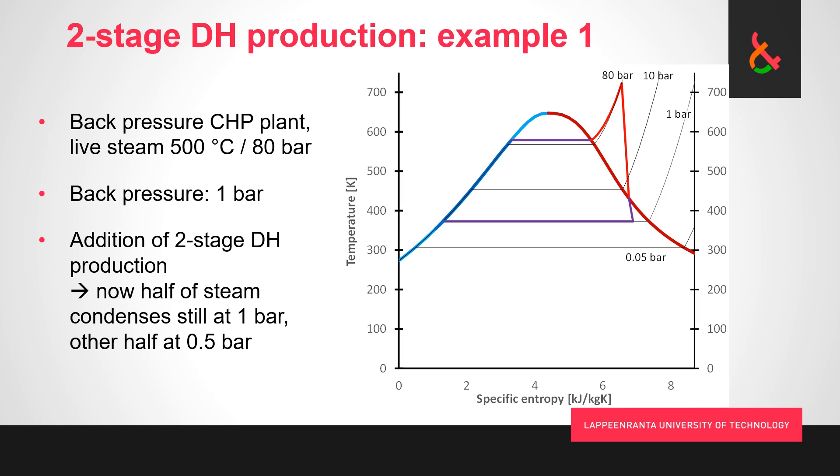We can't get to 0.05 bars, but what we can do if we add two-stage district heating production is that with the addition of a second condenser, the one that operates at lower pressure preheating the return water, we might get to around half a bar. Not a huge deal perhaps, but still substantial and non-negligible, so we want to do this if there is the option.